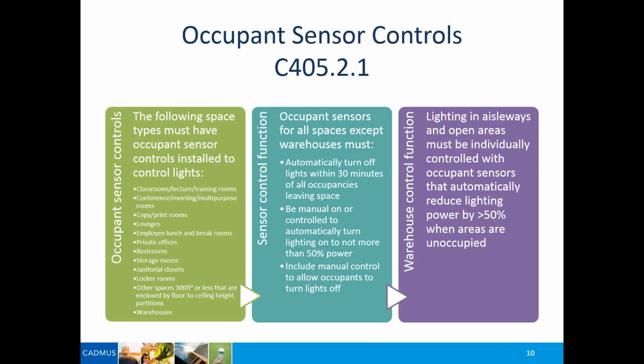You also need to have a manual on to control the lights in that space. So it would be a manual on and automatic off. If you don't have the manual on and the occupancy sensor turns the lights on, you can't turn it on to more than 50% power. And then you can always increase the power, obviously. So there are some requirements on how the lights are to be turned on in the space. With manual on, if there's already enough daylight or enough light in that space, you don't need the light to come on, and it's up to the occupant to turn the lights on using a manual control. And Eric? Yes.